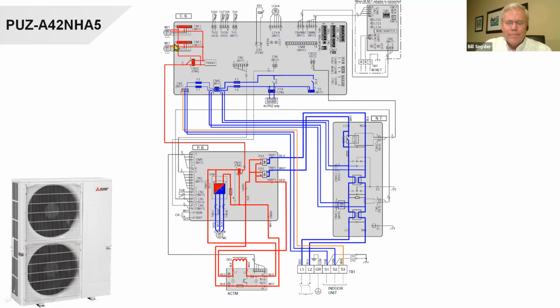What that means is, if we would actually take the back off the motor, with the shaft out the one end, you'd pull the back side off. If you could do that and look inside, you'd see a little electronic circuit board where your DC voltage goes. Coming out of that circuit board, you will see 3 terminals labeled U, V, and W that go into the windings of the motor. So those are actually a 3-phase type wound motor, and we're feeding it with DC.